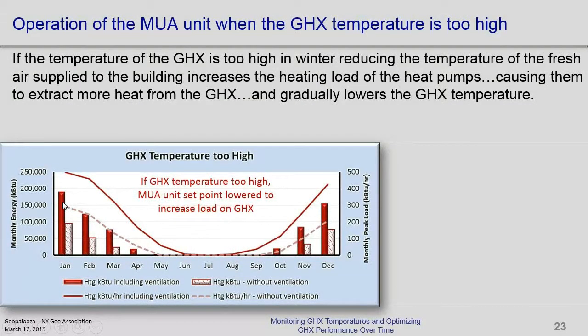If the temperature is too high, they'll reduce the set point of the makeup air unit. In other words, instead of supplying 70-degree air or neutral air to the building, they may only supply 65-degree air. What that does is increase the heating load for the heat pumps. They now have to heat some of the makeup air because it's a little cooler coming in. That extracts more energy from the ground loop and cools it off a little bit more. So if it's too high in January, he lowers the set point on the makeup air unit.